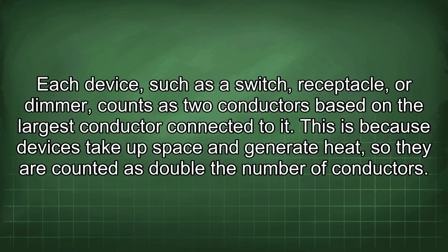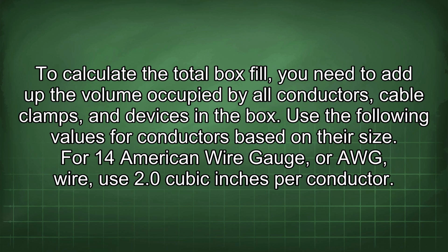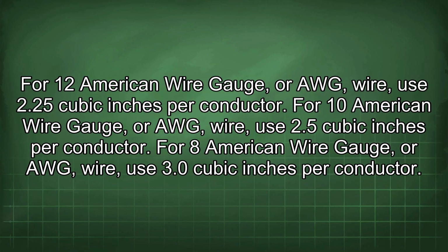Each device, such as a switch, receptacle, or dimmer, counts as two conductors based on the largest conductor connected to it. This is because devices take up space and generate heat, so they are counted as double the number of conductors. To calculate the total box fill, you need to add up the volume occupied by all conductors, cable clamps, and devices in the box. Use the following values for conductors based on their size. For 14 American wire gauge, or AWG, wire, use 2.0 cubic inches per conductor. For 12 AWG wire, use 2.25 cubic inches per conductor. For 10 AWG wire, use 2.5 cubic inches per conductor. For 8 AWG wire, use 3.0 cubic inches per conductor.